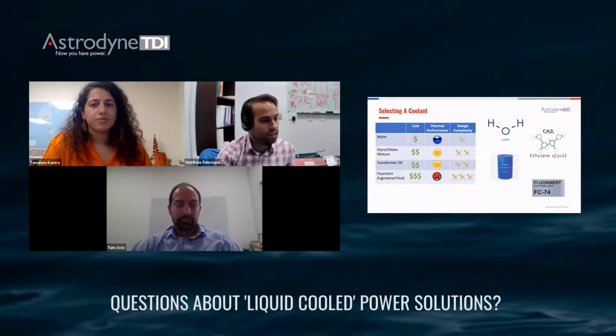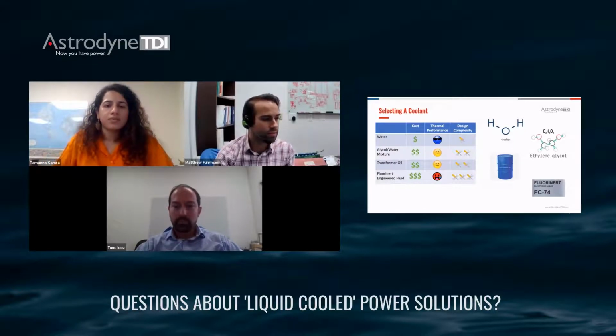In that application, we'd recommend a glycol and water mixture, where you can adjust the percentage of glycol to water based on the application. If you're going down to temperatures of minus 40 degrees C, you'd increase the glycol content to 60%. However, the trade-off is that glycol doesn't have as good thermal performance—typically you'll see higher temperatures in your components with glycol. So that's some of the design consideration you'd have to make there.